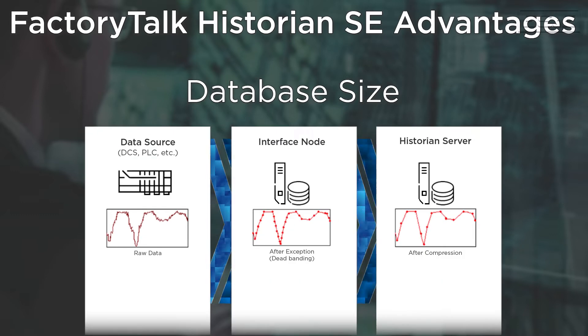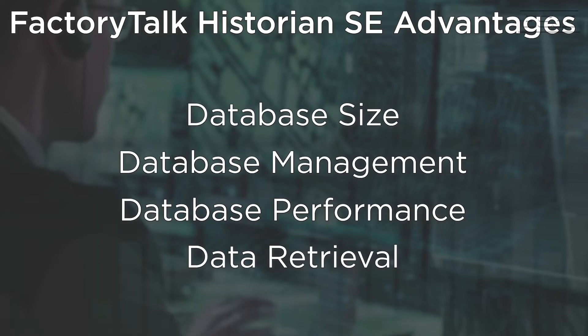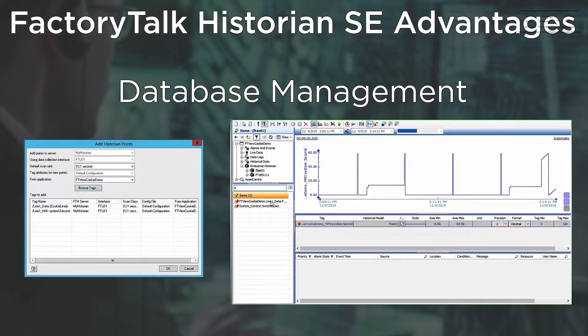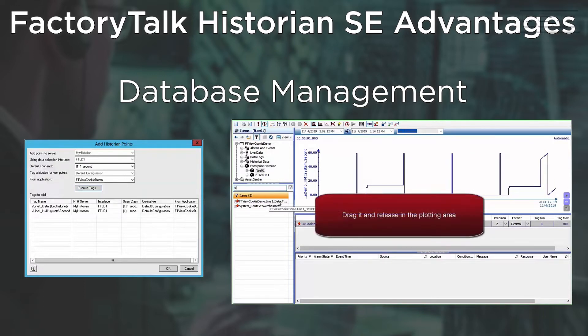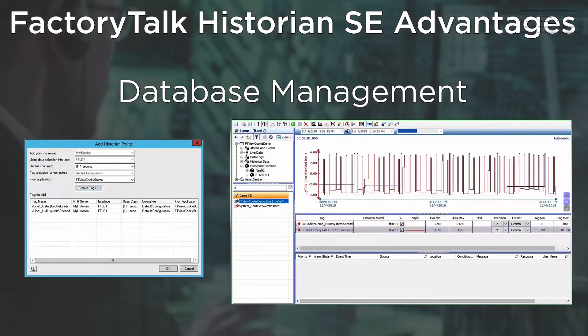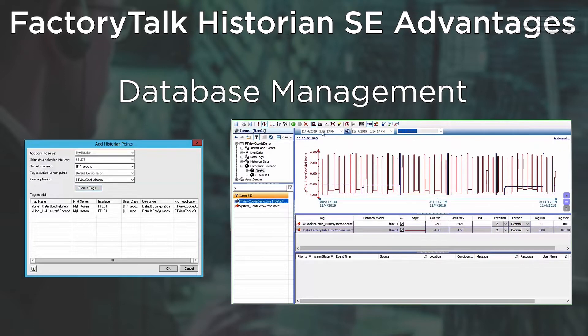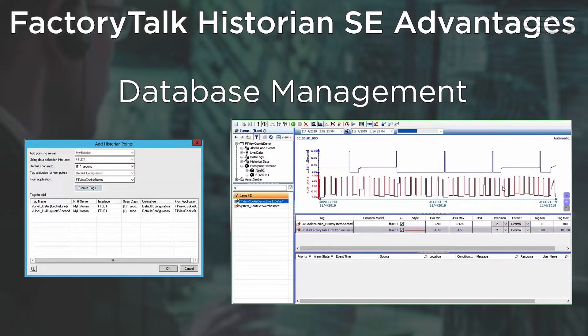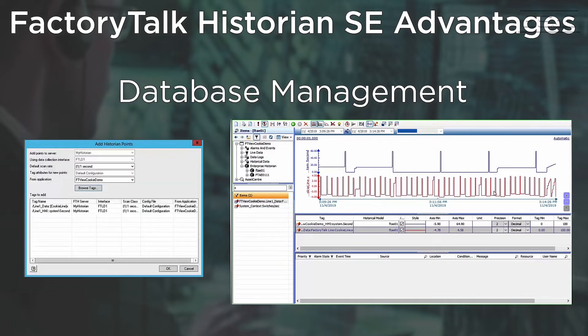Historian SE runs compression and makes that determination — parameters which you define. If the data hasn't changed, why store it? By doing that, it makes the other advantages come into play. Database management, for one — with the data store files being so small, it's much easier to manage those files as far as archiving them. With a relational database, you can build up a lot of data and then have to run SQL statements to clean that data up or back it off the server. Historian SE makes it easy from its interface to deactivate those archives and just copy them over.